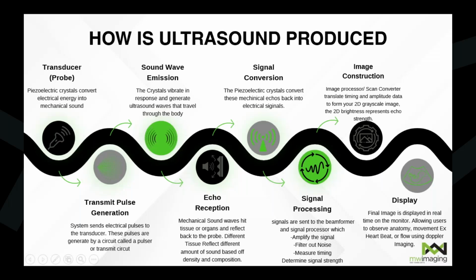All right, how is ultrasound produced? The core component to ultrasound and how it's produced is the transducer. Inside the transducer, you have piezoelectric crystals that convert electrical energy into ultrasound or mechanical energy, and vice versa, mechanical ultrasound energy back to electronic signals. In order to do this, the system sends out a transmit pulse. It sends electrical pulses to the transducer. These pulses are generated by a circuit called a pulser circuit or a transmit card inside the ultrasound system. Once this electrical pulse hits the crystal, it vibrates in response and generates an ultrasound wave that travels through the body.